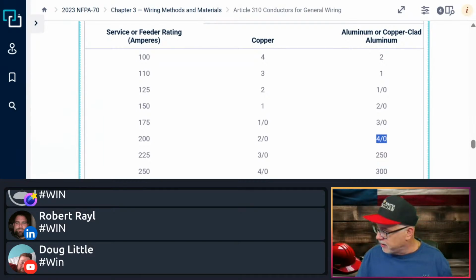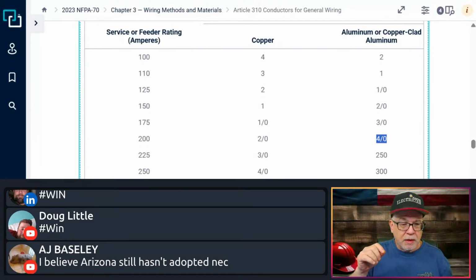Most people for the SE cables are just going to buy aluminum. They'll get a 4-aught aluminum, and I can promise you, it's hard to believe some of these states still aren't adopting things. Yeah, don't get me started. I don't get it. Different states, but anyway. So typically in that SE cable, the grounded conductor will be no more than 2 sizes smaller, which would be 4-aught, 3-aught, 2-aught. So that's why you have two 4-aughts and a 2-aught. That's typically what a manufacturer will do, in case you didn't know. All right, so that's that.